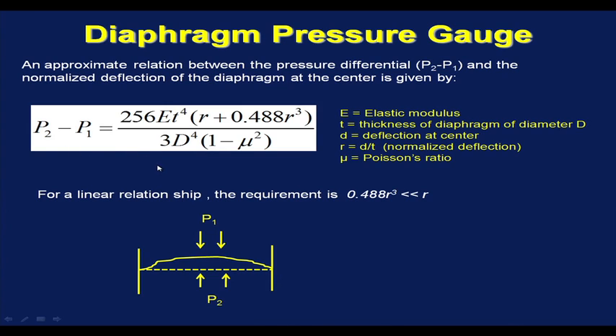So, the deflection of the diaphragm at the center depends on elastic modulus of the material of the diaphragm, thickness of the diaphragm, diameter of the diaphragm and the Poisson's ratio. In this equation, E is elastic modulus, T is thickness of diaphragm, R is normalized deflection, which is deflection at the center divided by thickness of the diaphragm, and D is the diameter of the diaphragm and mu is the Poisson's ratio of the diaphragm material.